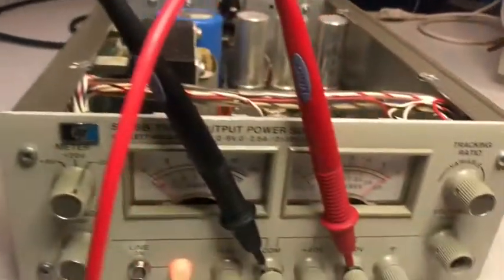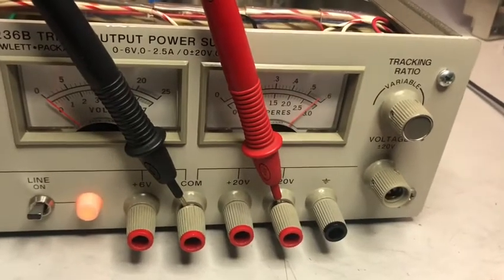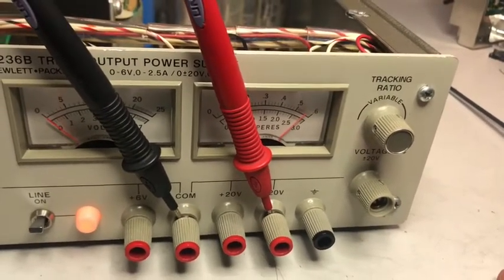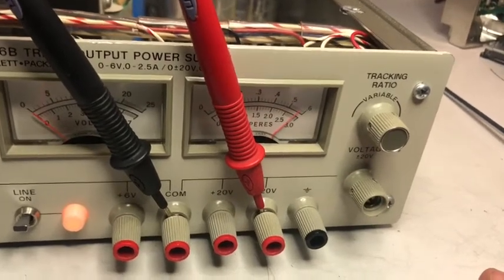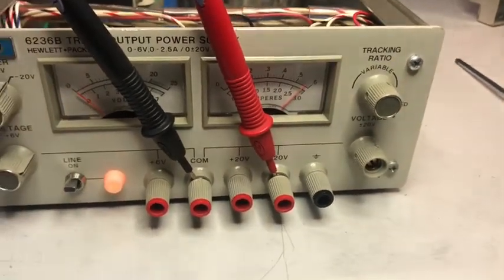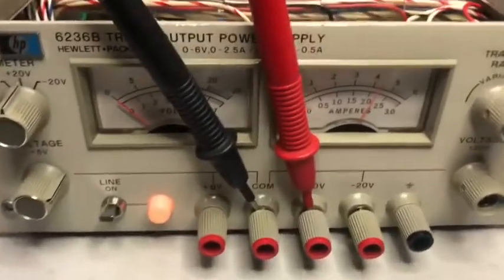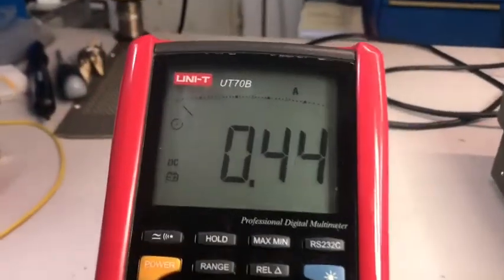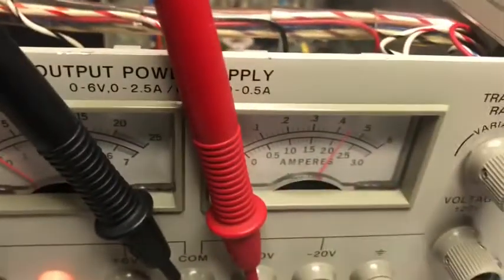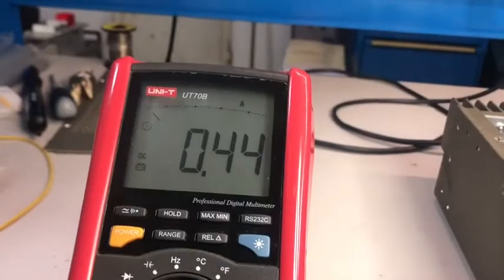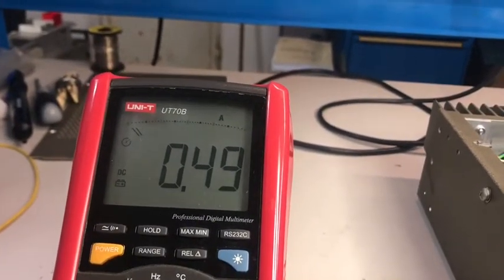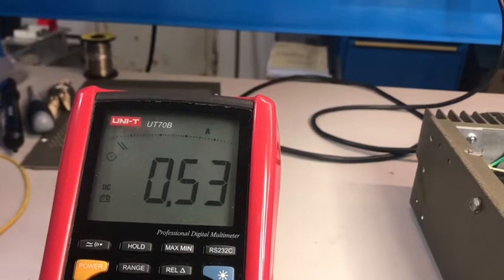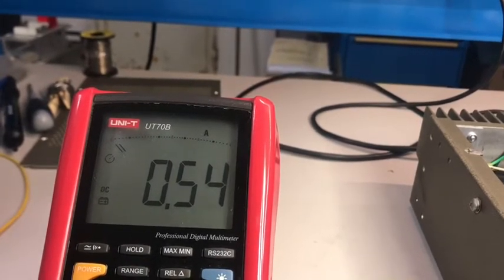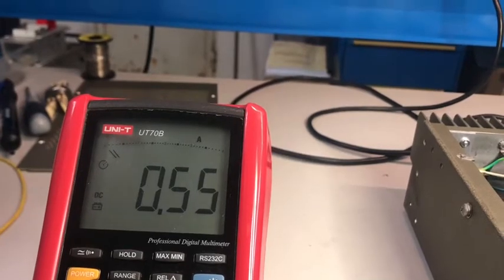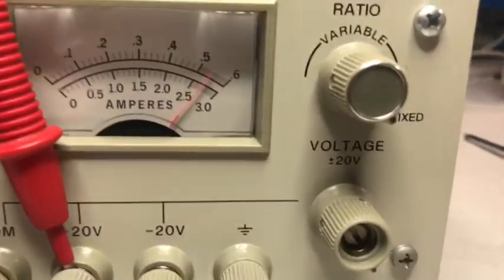So what I'm going to do is change to +20 and see the current limit on that section. Let me change the position. Okay, I have just changed it to +20, and as you can see it's regulated to 0.44, so it's a little bit out. I'm going to increase it to 0.55. That's okay, that's perfect.